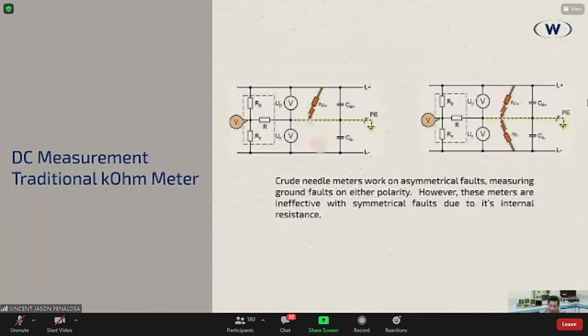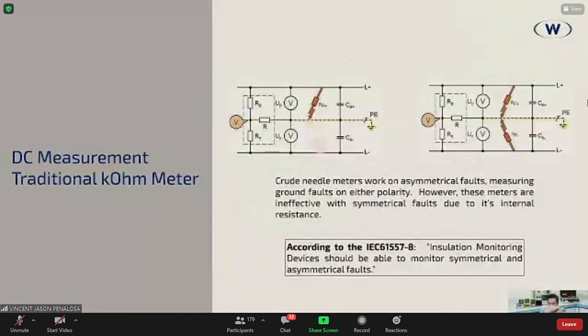In fact, again, this is also in the standards. Again, it's IEC 61557-8, where an insulation monitoring device should be able to tell you, or discriminate, whether the fault is symmetrical or asymmetrical or both. It should be able to discriminate positive or negative or both. Okay, so there. Now there it is. Sorry, kind of jumped myself there.